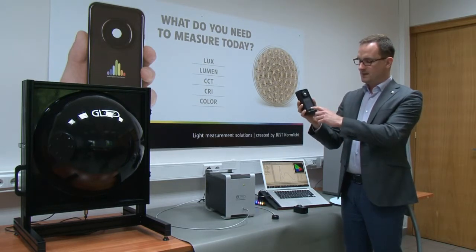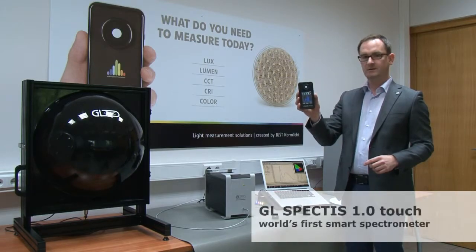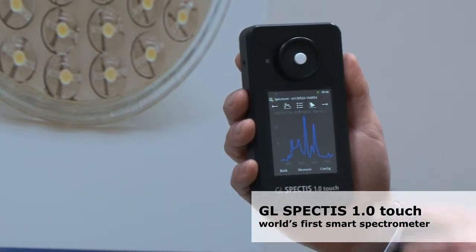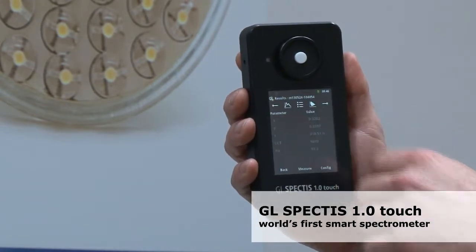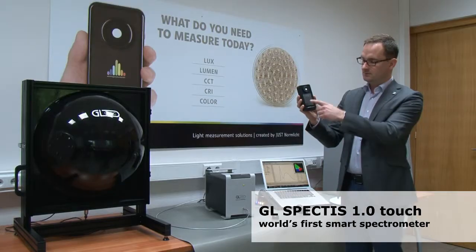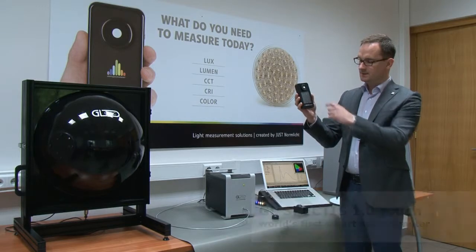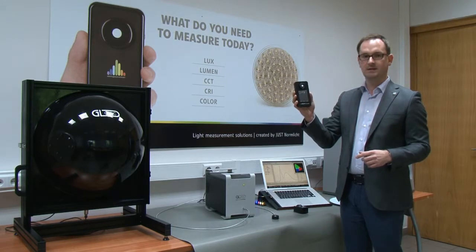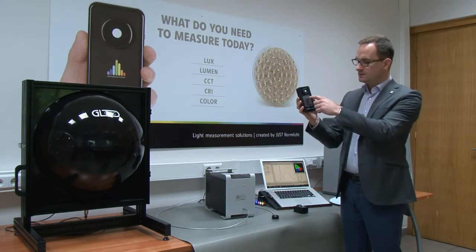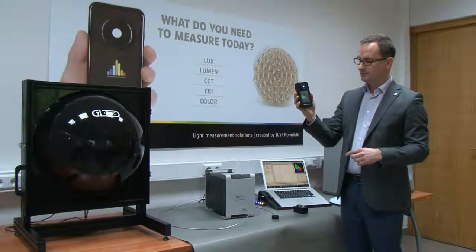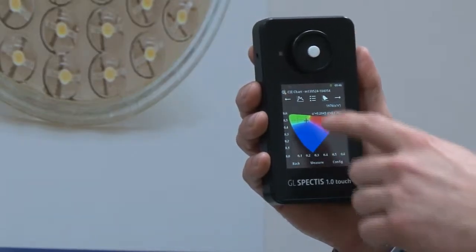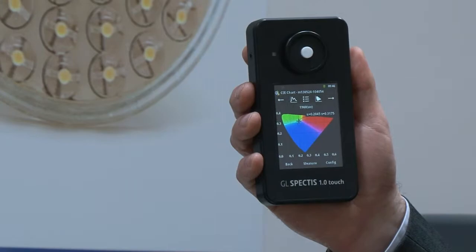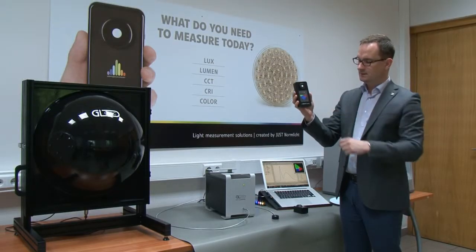I can simply make the measurement and show you the spectral power distribution. We are also providing listed selected values which are calculated: XY coordinates for color, lux value, the illumination level, CCT correlated color temperature, and CRI which is the color rendering index averaged. On this device we are also providing information on color coordinates according to different CIE standards, as well as the visual representation of these chromaticity diagrams.